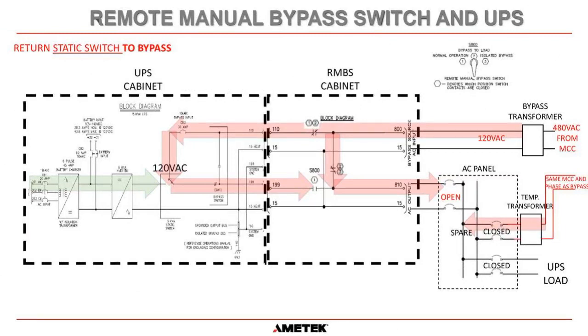And then what we do is return. We have to do this: return the static switch to bypass. Remember, that's the switch that doesn't move. It's the electronic switch that's operated by a push button on the front of the UPS. We press the button that says bypass to load. That is essential for these next steps.